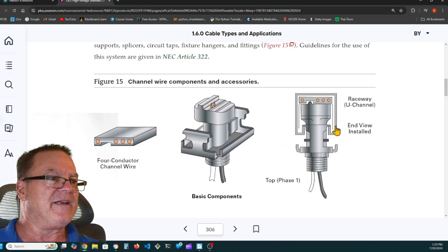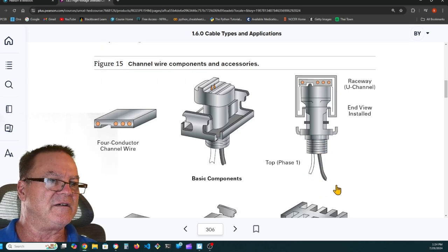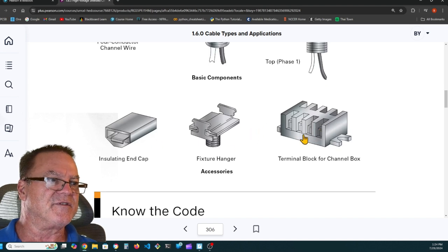So it's a lot like Unistrut in that it's a metal box, and inside the metal box they have the conductors insulated from the metal. And then when you want to put one of these trolleys in, you can see these two prongs will tap into the neutral and one of the hots. There's a four conductor channel. It'll tap into the ones that it needs, and you'll be able to put lighting fixtures on this. It has different taps. It has a terminal block where you can bring the power to it.